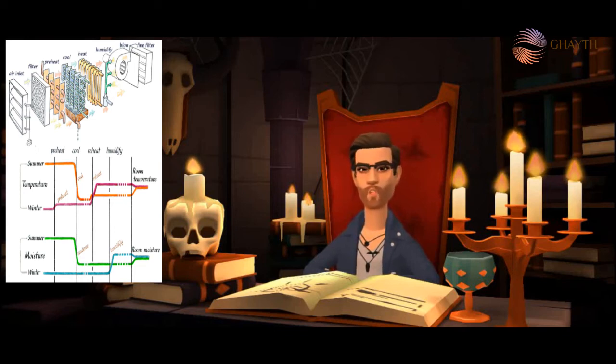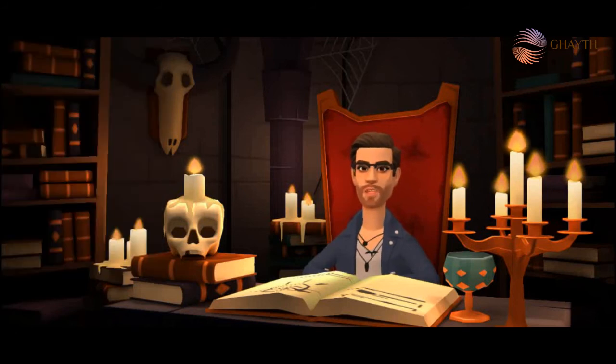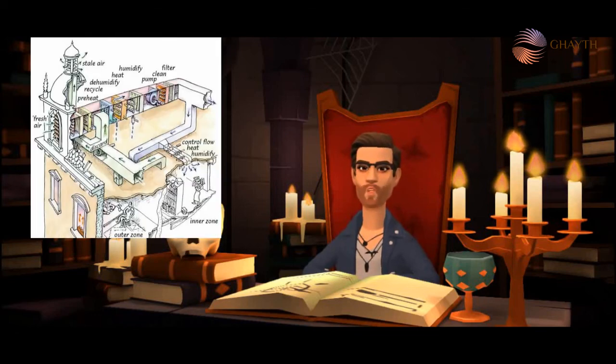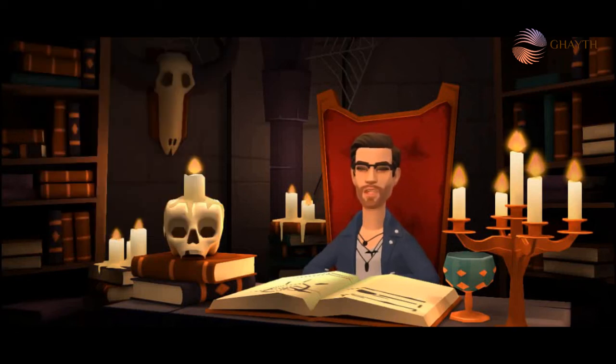Rating is based on how many Btu per hour are removed for each watt of power it draws. For room air conditioners, this efficiency rating is the energy efficiency ratio, or EER. For central air conditioners, it is the seasonal energy efficiency ratio, or SEER. Room units built after January 1, 1990, need to have an EER of 8.0 or greater, an EER of at least 9.0 if you live in a mild climate, and an EER over 10 for warmer climates.